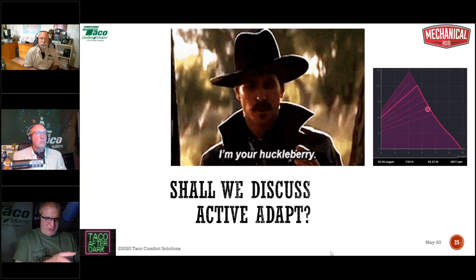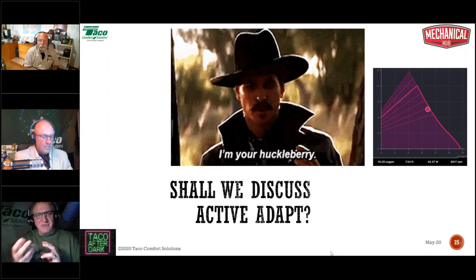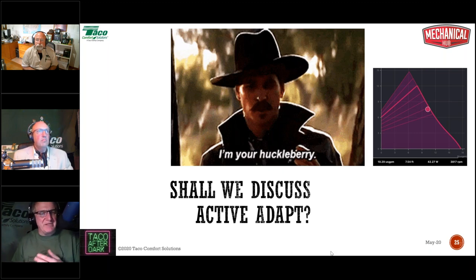So it's not that this application is best for delta P and this application is best for delta T. I think it's just a matter of, you've got good, which is a properly sized, regular standard efficiency pump. You've got better, which is delta P, and you've got best, which is delta T. Again, it goes back to how much value you're getting for the extra cost of the delta T pump. Again, with a smaller system, there's not as much of a difference, not as much variable speed variation. The value may be somewhat dubious there. You may be spending a lot more money, but you may not be getting that much benefit from it. So that's kind of how I would look at it.